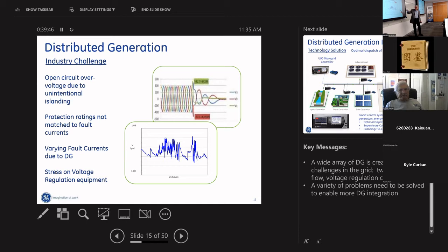But the other thing is the fault currents vary with the distributed generation. Is the sun always shining on the PV panels? No. What if a fault occurs on a very cloudy day? There'd be no load side contribution of fault. What if a fault occurs when the sun's brightly shining and all those PV panels are generating? There could be a significant load side contribution to the fault. How do you set the relays then? It depends when the fault occurs. So, varying fault currents due to the intermittency of the distributed generation. All right.